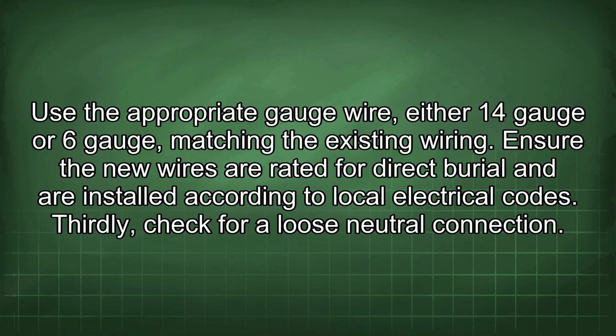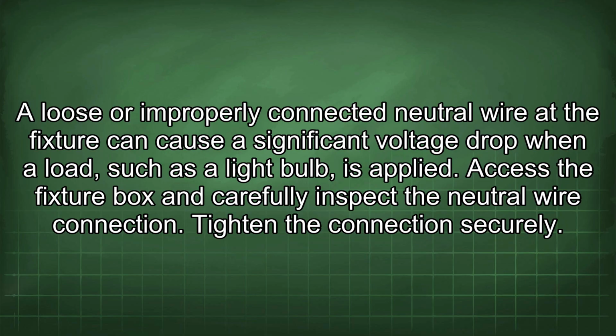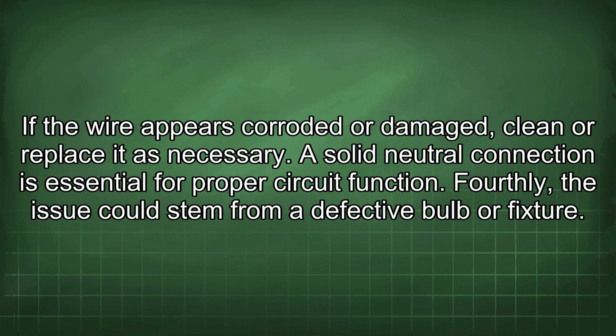Thirdly, check for a loose neutral connection. A loose or improperly connected neutral wire at the fixture can cause a significant voltage drop when a load, such as a light bulb, is applied. Access the fixture box and carefully inspect the neutral wire connection. Tighten the connection securely. If the wire appears corroded or damaged, clean or replace it as necessary. A solid neutral connection is essential for proper circuit function.